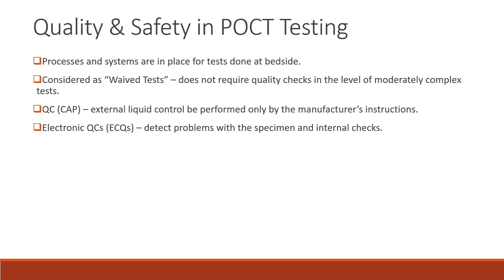Quality and safety in POCT testing. There are processes and systems in place for testing done at bedside. These POCT tests are considered waived tests, so they do not require quality checks at the same level as moderately complex tests done in the clinical laboratory. For QC, according to the College of American Pathologists, external liquid control can be performed only per the manufacturer's instructions. Some POCT devices have electronic QCs or EQCs that detect problems with the specimen and have internal checks.